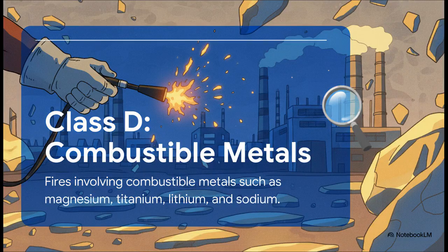And finally, we have the really specialized one, Class D. These fires involve combustible metals, stuff you might find in an industrial plant or a high-tech lab. These are no joke. They're incredibly dangerous because they can react violently, even explode, with water or other common extinguishers. They need a very specific dry powder agent.